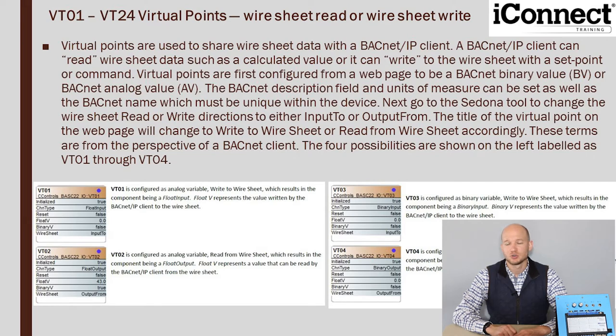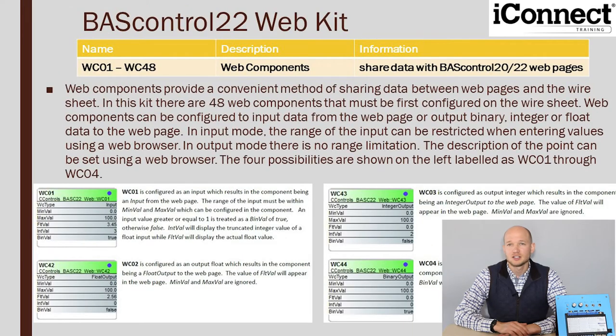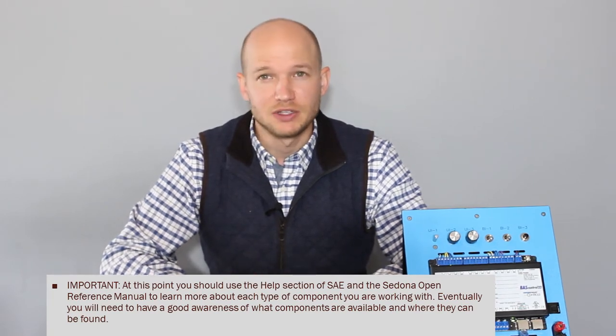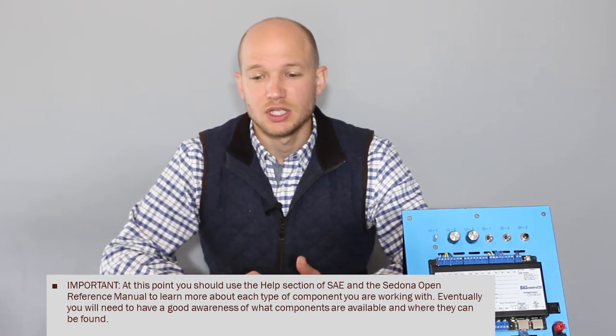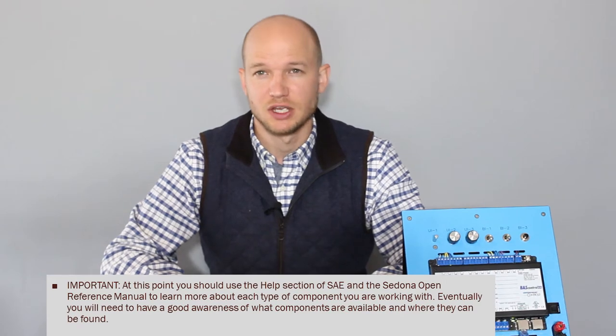Here we show a little more information on the virtual points. These are utilized to share wire sheet data with BACnet and IP clients, and those can read or write. The last components I wanted to touch upon are the web components. In this controller we can program 1 through 48, and like the virtual points these have a wide range of usage. If you'd like to learn more, you can use the help section in SAE or the Sedona open reference manual, which takes a deep dive into individual components and their functions.